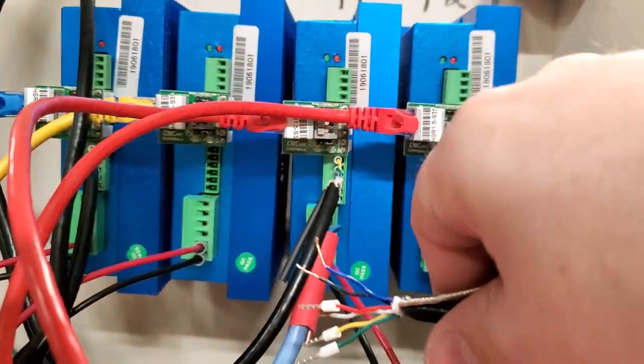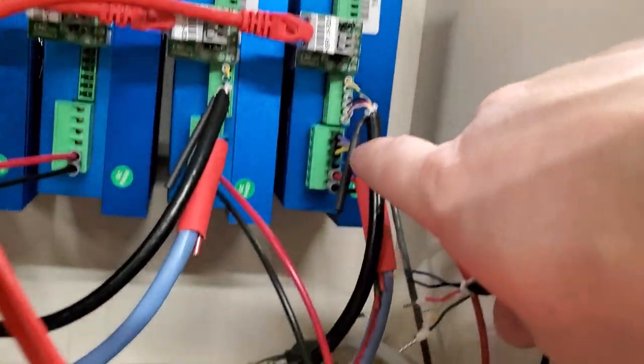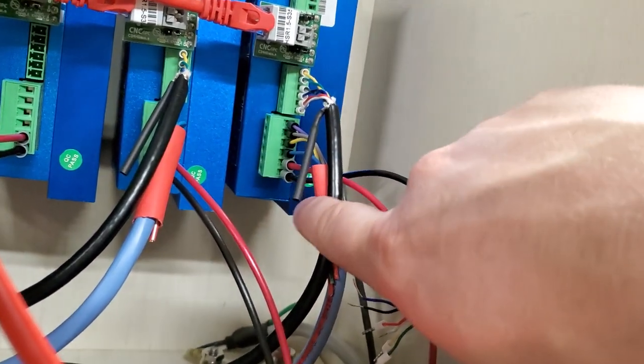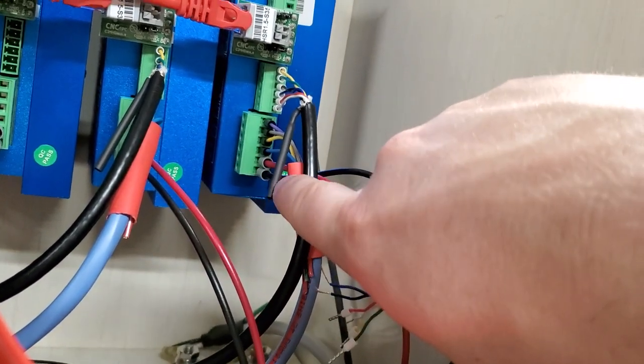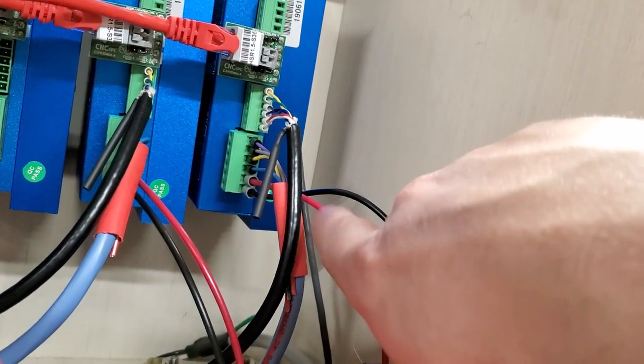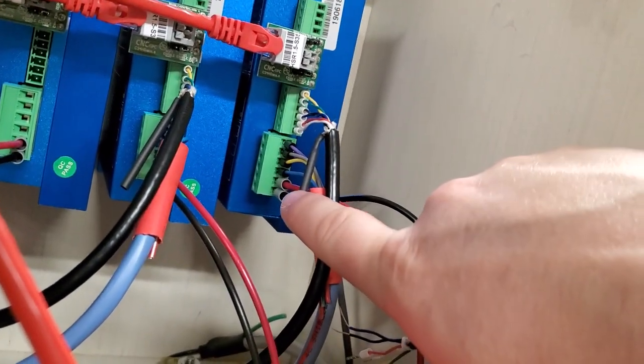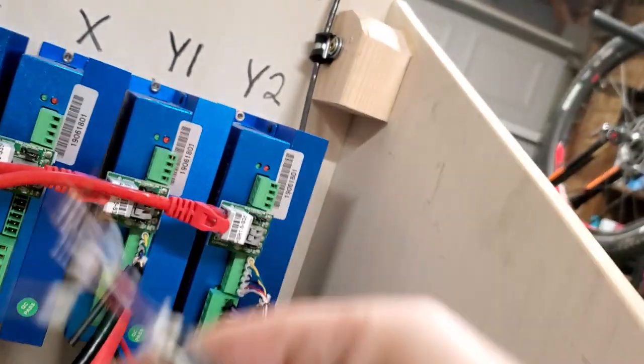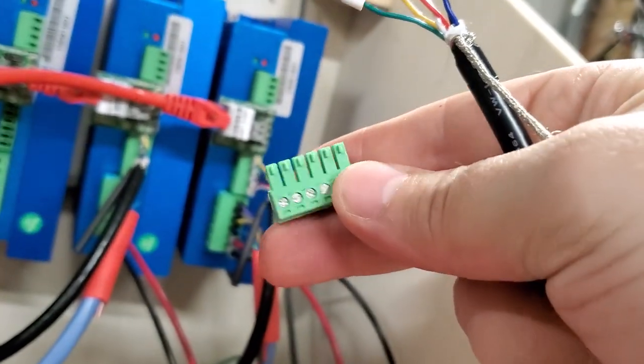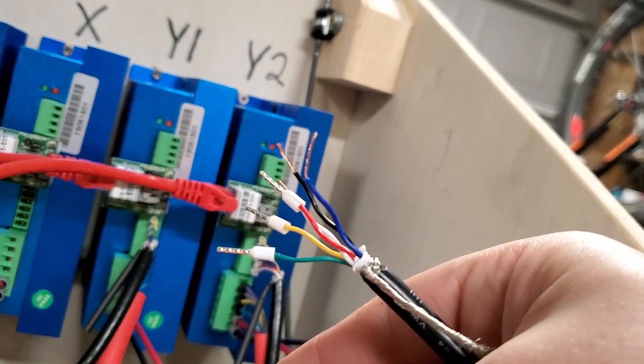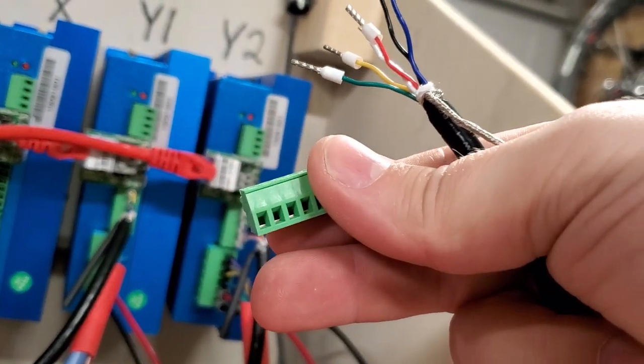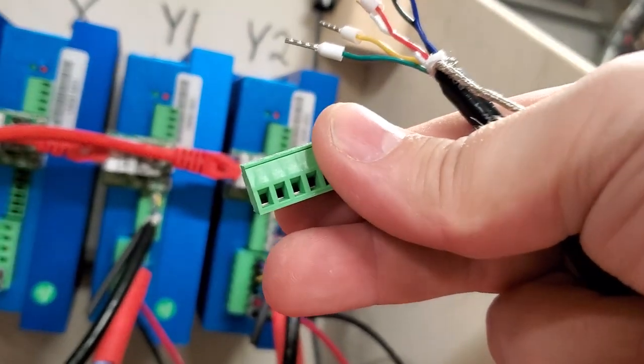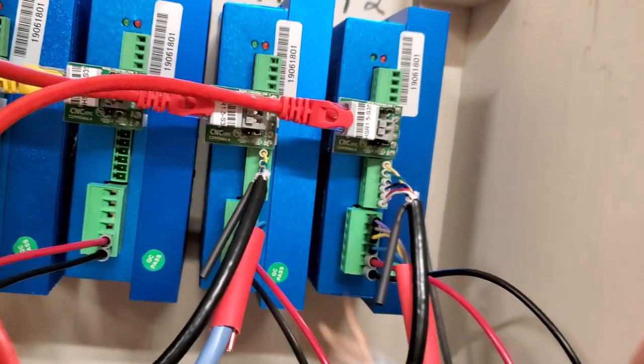I think this is my last one that I'm working on, but this is a perfect example of wire ferrules. Those are power lines, 48 volt DC power lines. These big guys right here, and you can see they're right next to each other on these tiny little blocks. Since they're right next to each other, you don't want even the tiniest little piece of copper extending from one port to the next, and you can tell it's very easy for that kind of thing to happen with these guys.